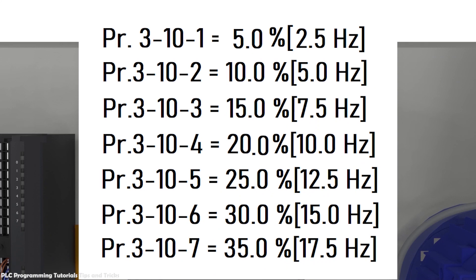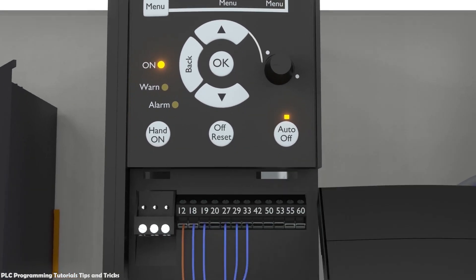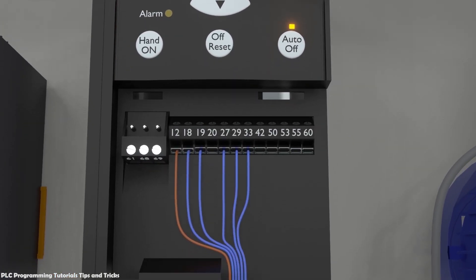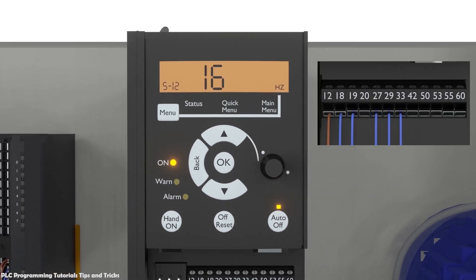We have entered seven different preset frequency references in the VFD. Now the question is how we can select these different frequency references using the PLC digital output signals. We can select the frequency references using the digital inputs of the VFD. There are three input terminals: 27, 29, and 33. We have to configure these terminals to preset reference selection bits. We will set parameter 5-12 to 16, which sets terminal 27 as preset bit 0.